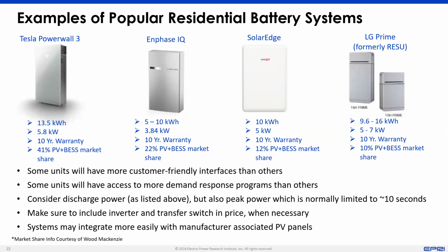Here we see the 4 most popular systems installed nationwide. Neither EPRI nor CalEHP is suggesting that you install these systems or that they are better or worse than any others - they are just the most popular when it comes to the photovoltaic and energy storage market share. The Tesla Powerwall, for example, is a 13.5 kilowatt hour, 5.8 kilowatt system - that's a little bit more than a 2-hour system. Enphase is about the same. SolarEdge is exactly a 2-hour system, and LG Prime, again, about the same. Most of these systems are approximately 2-hour systems.